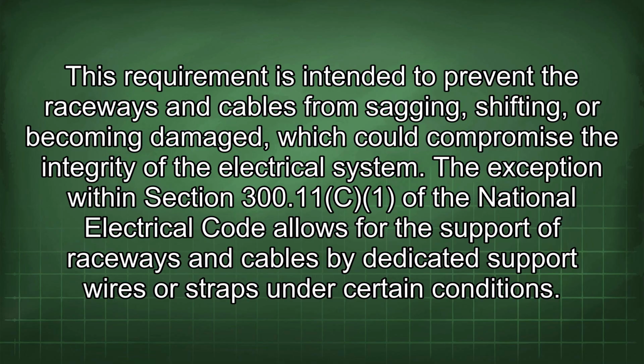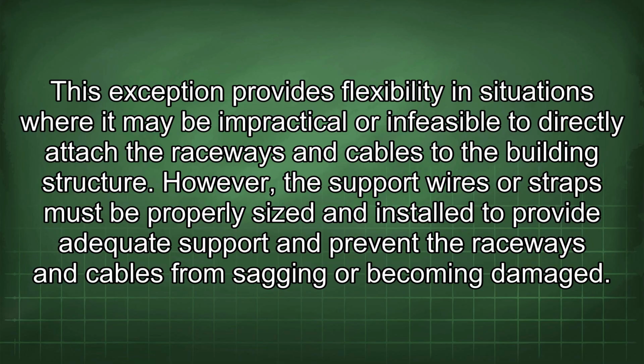The exception within Section 300.11(C)(1) of the National Electrical Code allows for the support of raceways and cables by dedicated support wires or straps under certain conditions. This exception provides flexibility in situations where it may be impractical or unfeasible to directly attach the raceways and cables to the building structure. However, the support wires or straps must be properly sized and installed to provide adequate support and prevent the raceways and cables from sagging or becoming damaged.